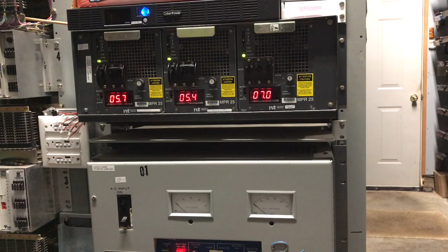The way the DC power system works in a telephone central office: the rectifiers carry the load of the office while there's AC power, and they're wired in parallel to the batteries. So if there's a commercial power failure, the switching equipment won't see a transition like on a computer UPS where you switch from line to battery — the batteries simply pick up the load.